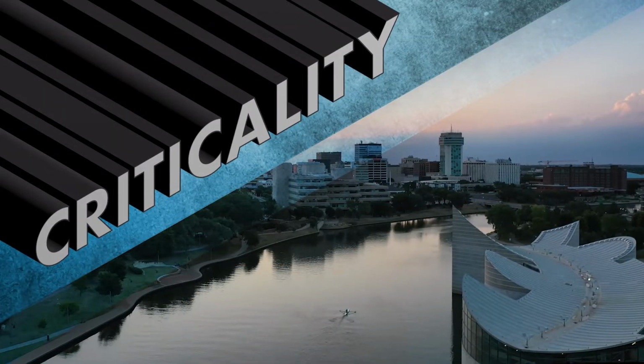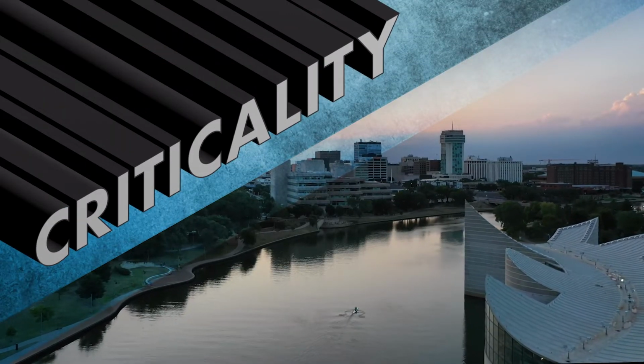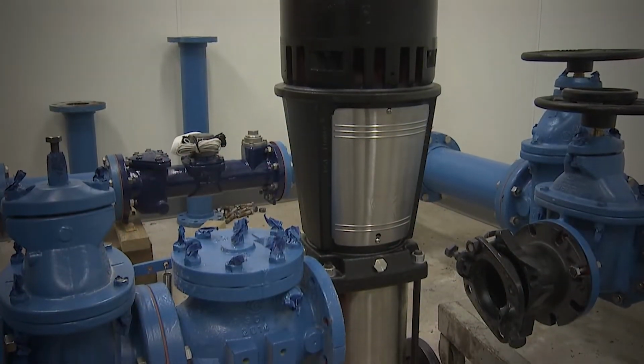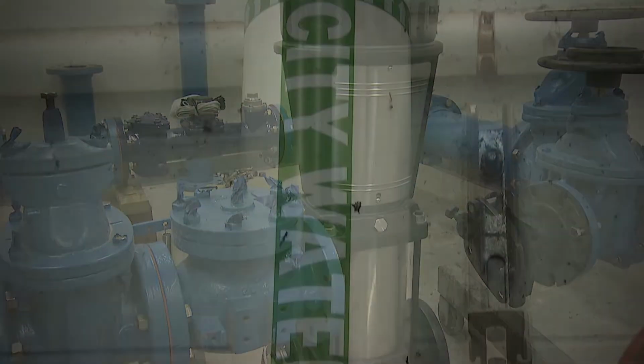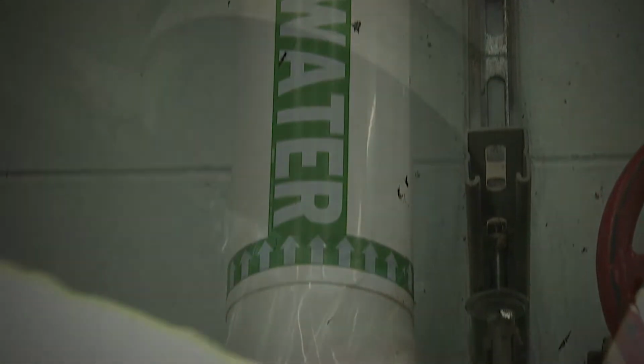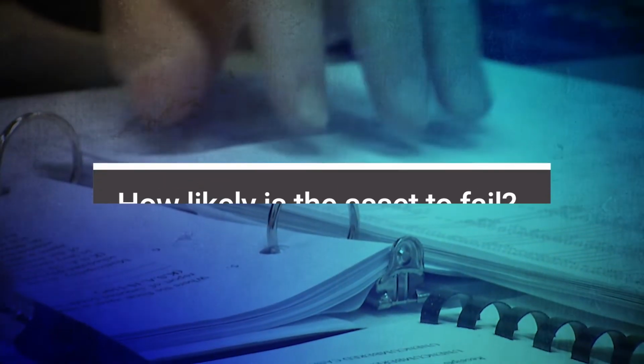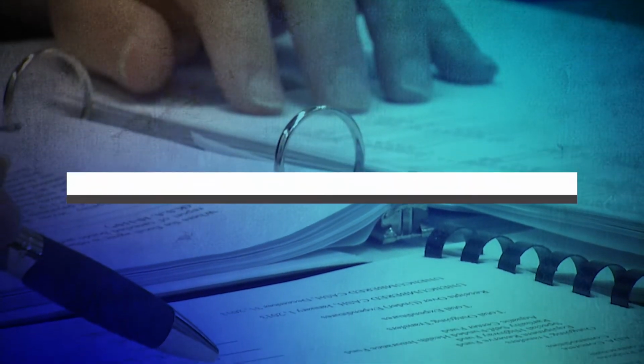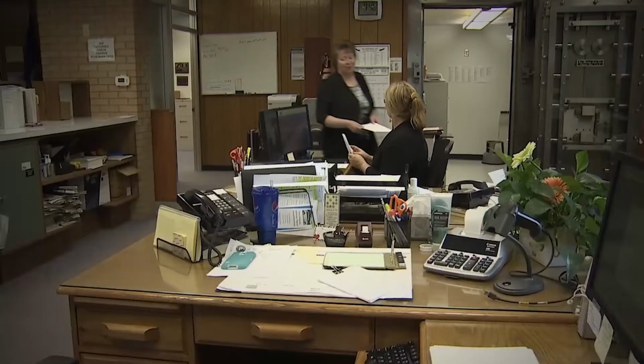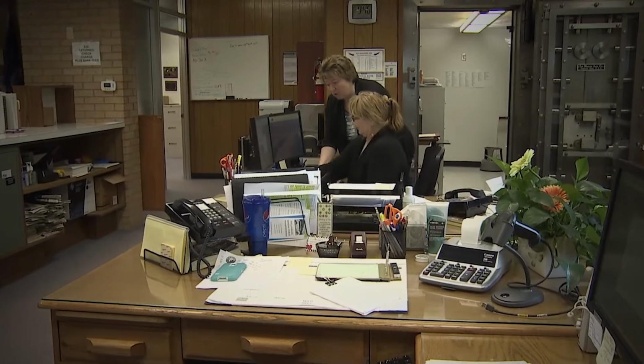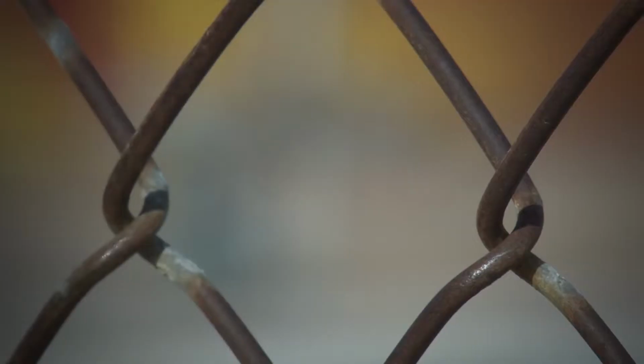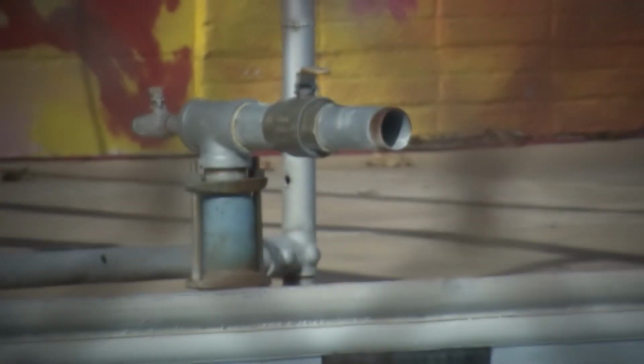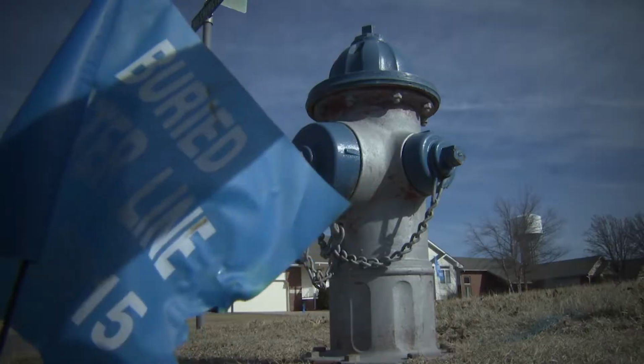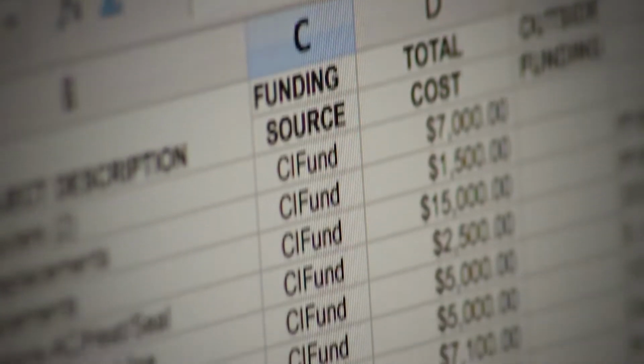Next is criticality. Not all assets are equally important to the utility's operation. Some are highly critical to operations and others are not. When determining criticality, 2 questions are important. How likely is the asset to fail, and what is the consequence if it does? Answering these questions will allow a utility to manage its risks and aid in determining the balance between expenditures for operations and maintenance, as well as for capital projects.